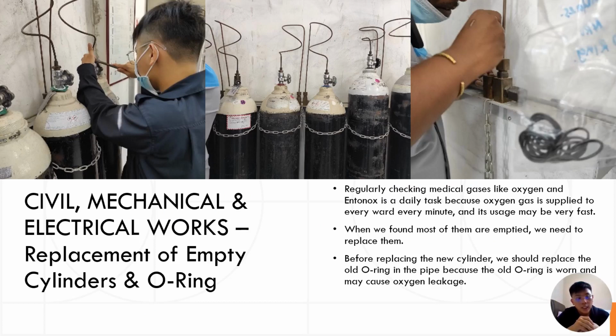Other than the electrical works, I also assisted in replacing the empty oxygen cylinder as well as the O-ring. Regular checking of medical gases like oxygen and Entonox is a daily task, because oxygen gas is supplied to every ward every minute, and its usage may be very fast. When we find most of them are empty, we need to replace them. Before replacing with the new cylinder, we should replace the old O-ring in the pipe, because the old O-ring is worn and may cause oxygen leakage. As you can see in the picture, Mr. Dhillon gave me some guidance on replacement of the empty cylinder and O-ring.